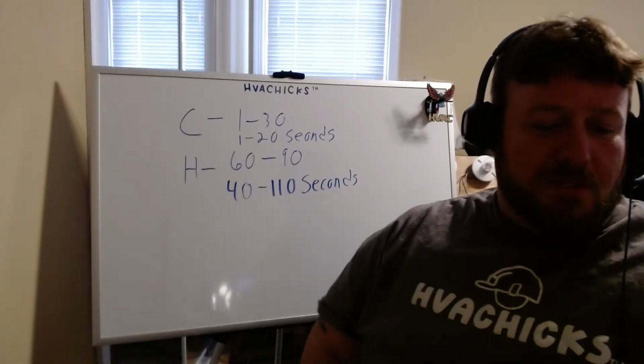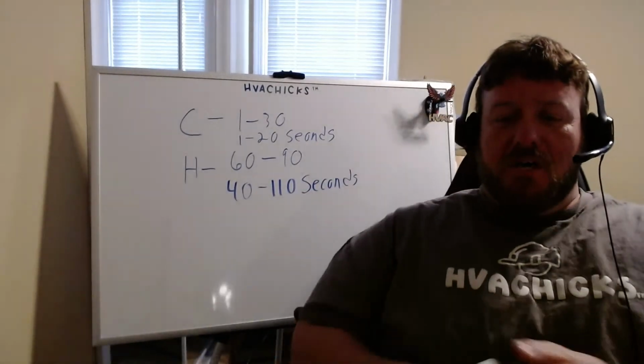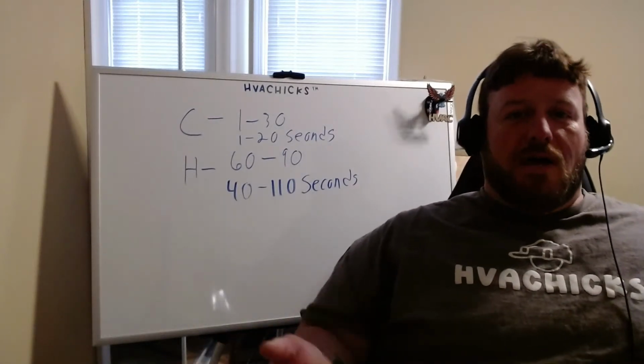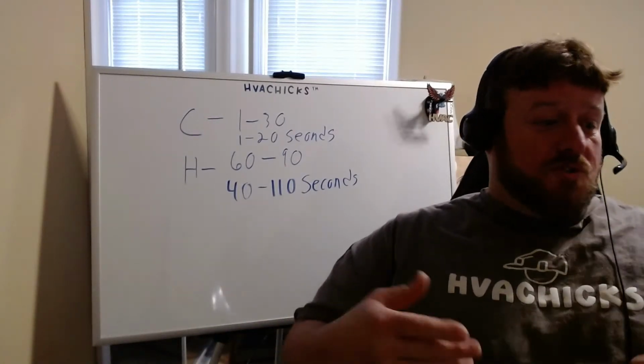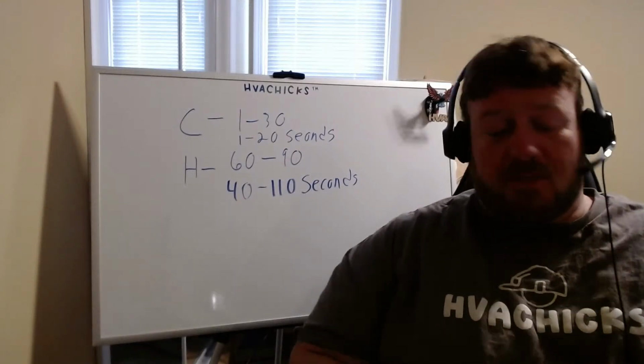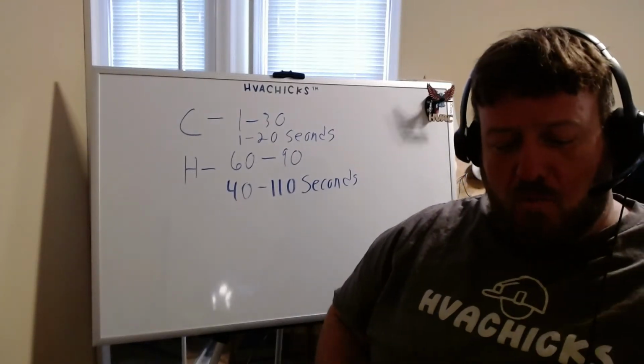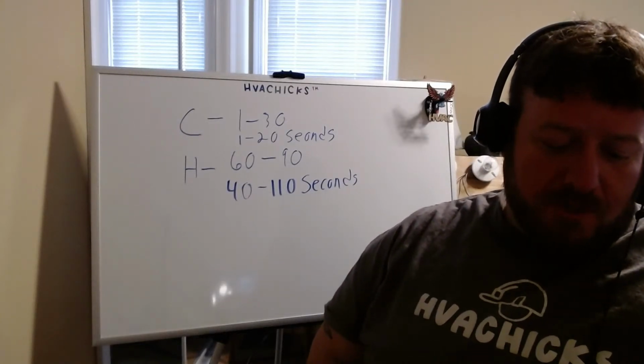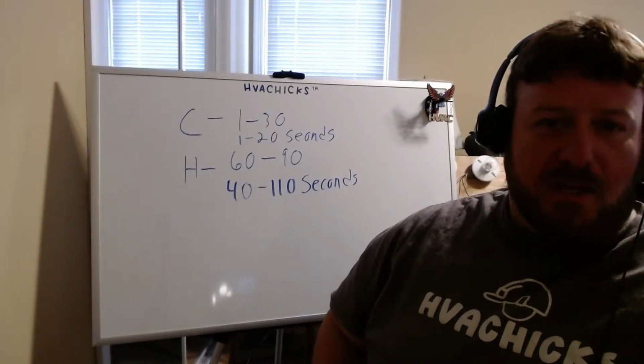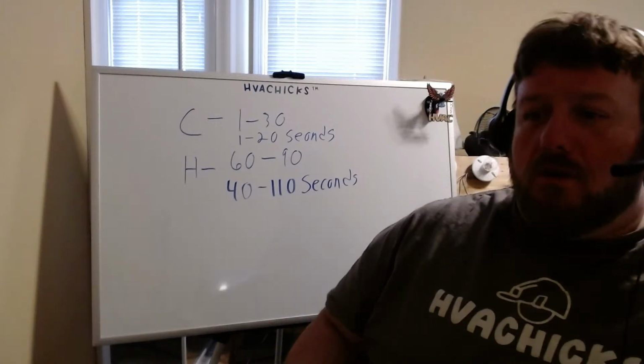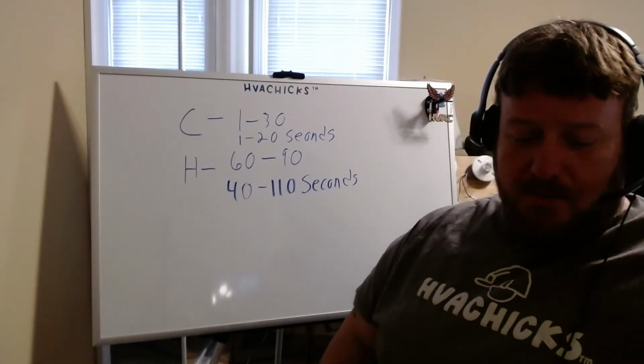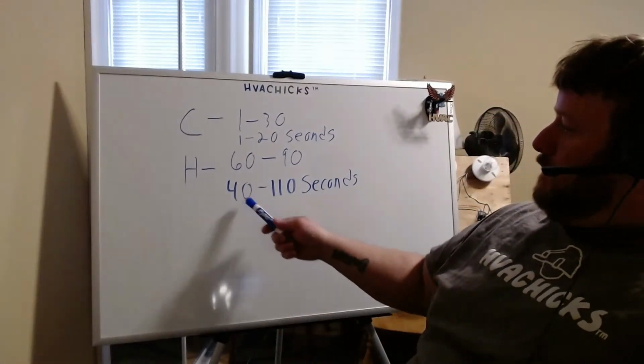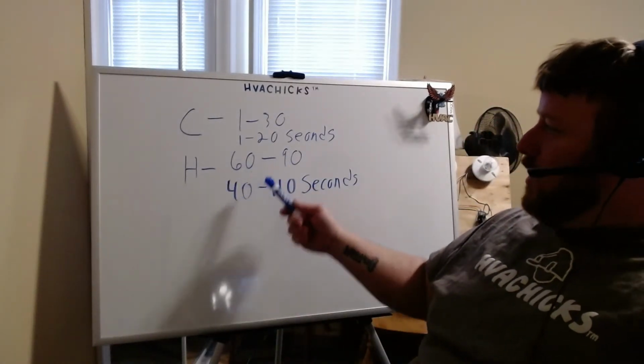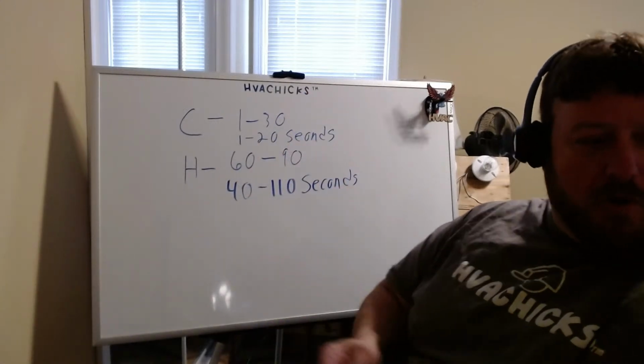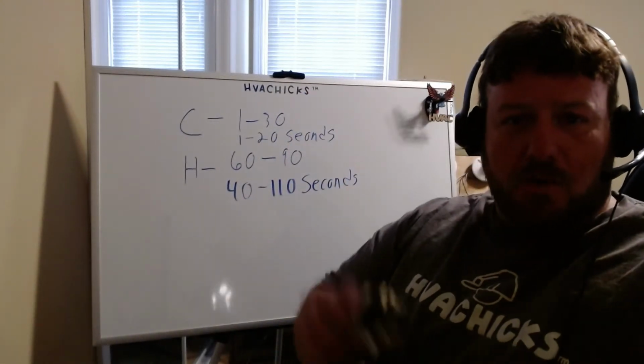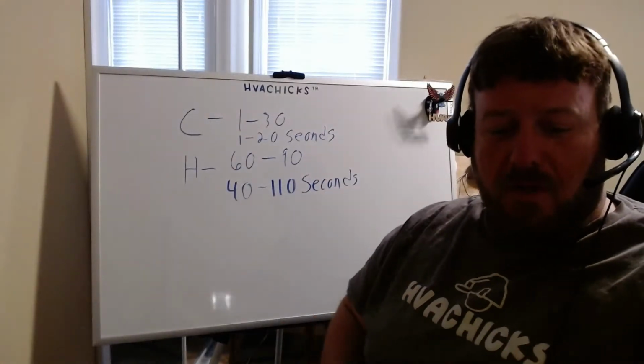Now, when you're messing with sequencers, you can buy aftermarkets, you can buy factories. If you have to get an aftermarket, try to find one that's as close to the numbers as possible. That is my best recommendation. You don't want to say, okay, well, the old heat up one was 60 to 90, let me put one that's going to take longer or shorter. You want to get the closest you can get. So 40 to 110, 60 to 90, it's close. 1 to 20, 1 to 30, they're close. So you can always find something that will match closely to a factory one with some aftermarket sequencers.